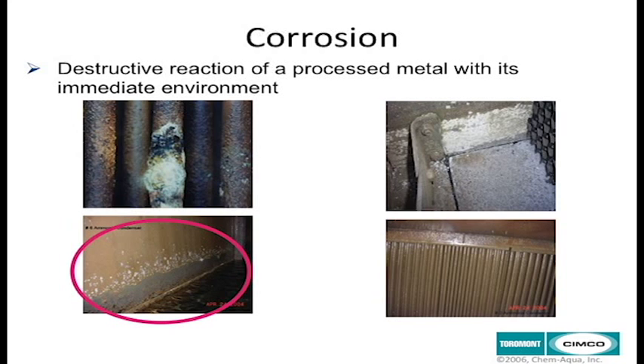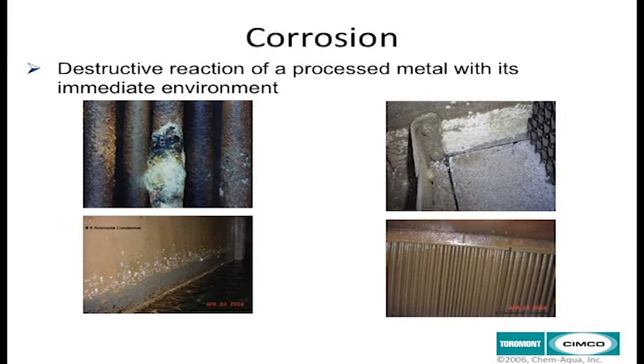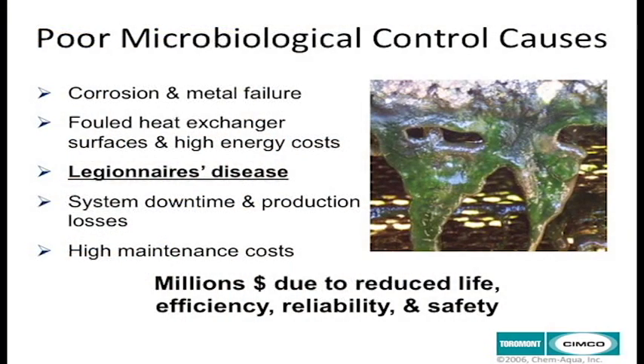Corrosion can also occur inside the cooling tower when there's microbiological attack. We call it microbiologically induced corrosion because the bacteria grow behind the sludge that builds up inside the cooling tower where the sump is. If you don't clean the sump and you allow the microbiological growth, they start eating the metal surfaces. You'll start corroding your sumps and your metal surfaces. So there are many things that cause corrosion in your cooling towers, which many people don't suspect. Causes of microbiological problems can lead to corrosion, metal failure, and fouled heat exchangers.